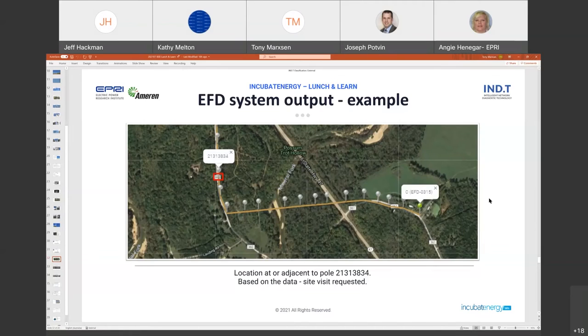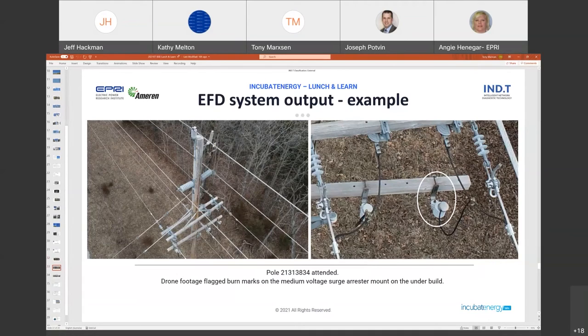Tony, if you'd go to the next slide, please. In this section, we identified that there was a problem on this pole, and they gave a very small geographical distance. They were sure it was on the pole, plus or minus 20 feet or something, so we were pretty confident to look on the pole. Had we not found anything, we would have expanded the search a little bit. But what we found, when the IND system says it's someplace, is another one of those things we were hoping to prove. You didn't have to spend an entire day looking for something that they found. It immediately found that surge arrestor, as you can see in the right picture, you can see the configuration of the pole, and the bracket has got some scorching or discoloration at a minimum.